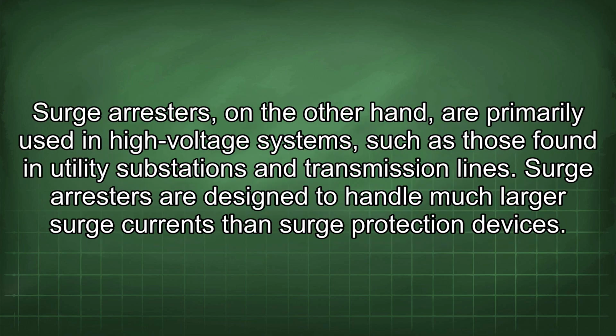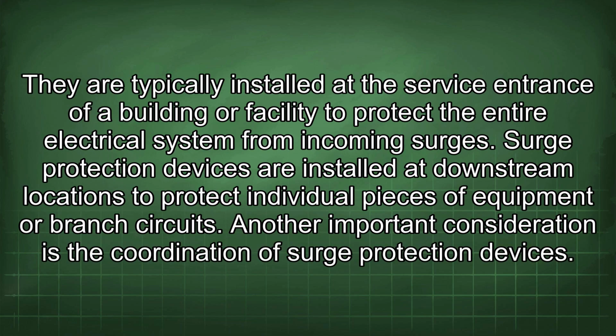Surge arresters, on the other hand, are primarily used in high-voltage systems such as those found in utility substations and transmission lines. Surge arresters are designed to handle much larger surge currents than surge protection devices. They are typically installed at the service entrance of a building or facility to protect the entire electrical system from incoming surges. Surge protection devices are installed at downstream locations to protect individual pieces of equipment or branch circuits.